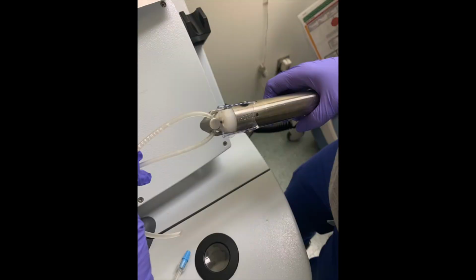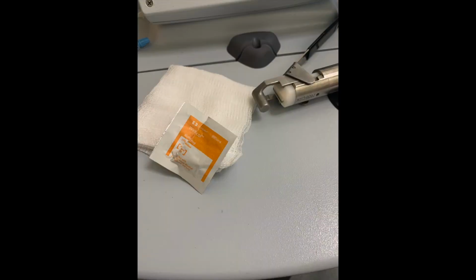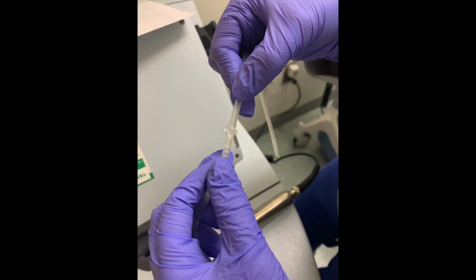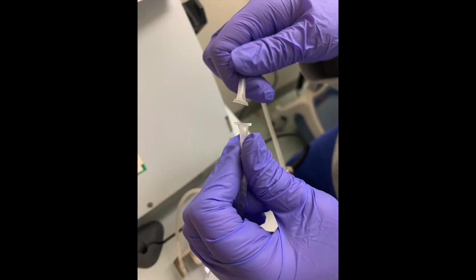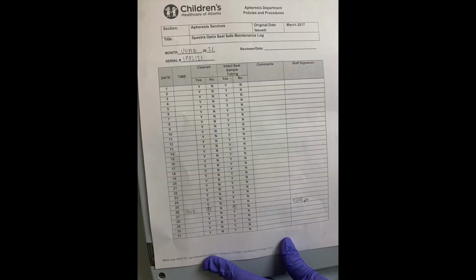Apheresis staff is responsible for the maintenance and quality control of the Spectra Optia Seal Safe system. Efficiency and safety are ensured through cleaning the sealer head prior to the first use of the day of collections and testing to confirm that the sealer makes an intact seal on collection tubing. Documentation of cleaning and quality control testing is then performed.